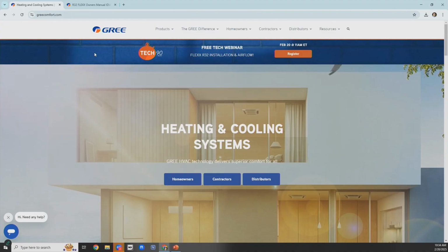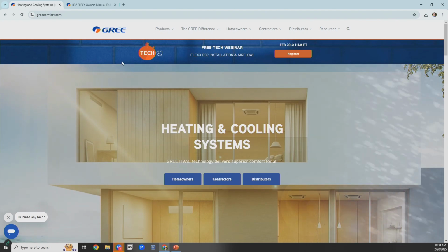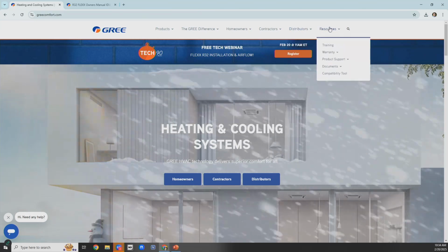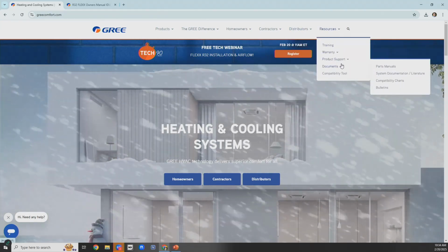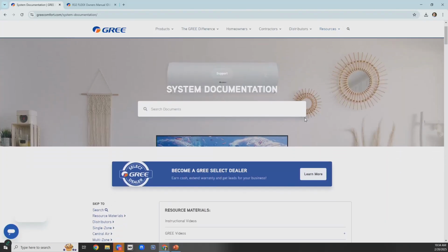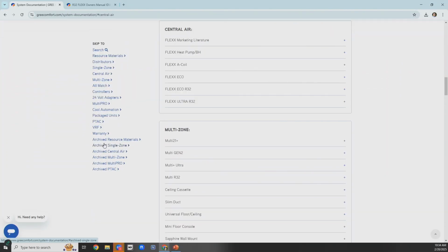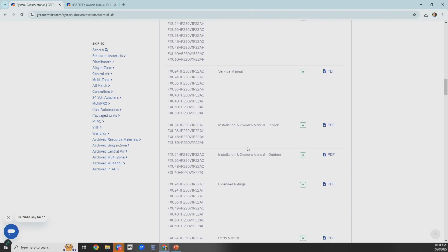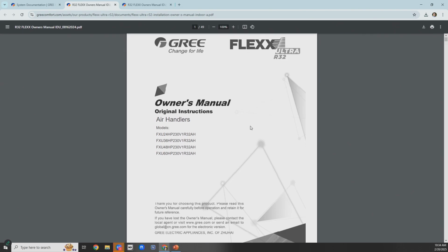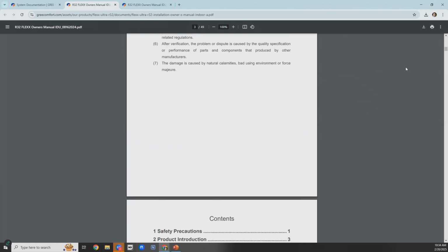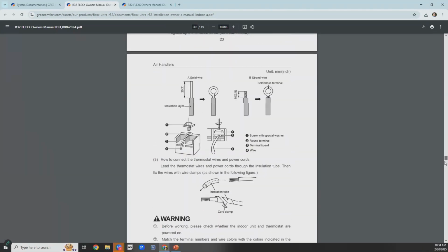That's a good question. Before I answer, we're going to refer back to the wiring diagram for the indoor-outdoor unit and a 24-volt thermostat. We're going to show you here on the website. If you go to our website at greecomfort.com, go under resources, then under system documentation, and click on that, you go to central air on the left-hand side. It's hyperlinked that way for you. Then you can go to FLEXX R32, and the manual we're going to want to pull up is the indoor installation owner's manual. We'll get that open, and we're going to look at the wiring diagram, which I believe is around page 30 something. So let us get there.